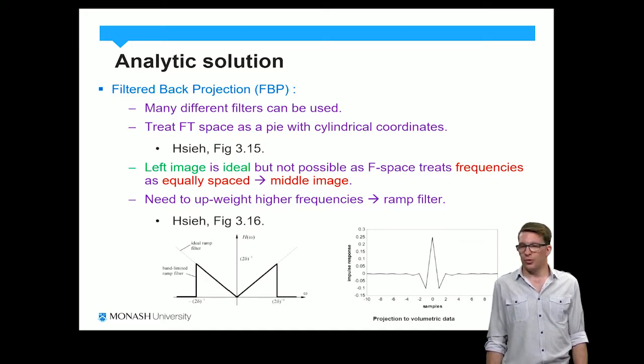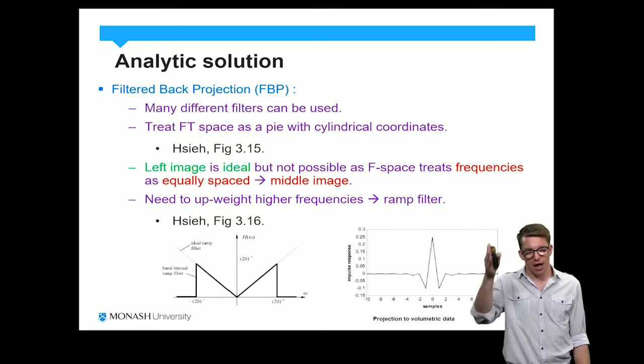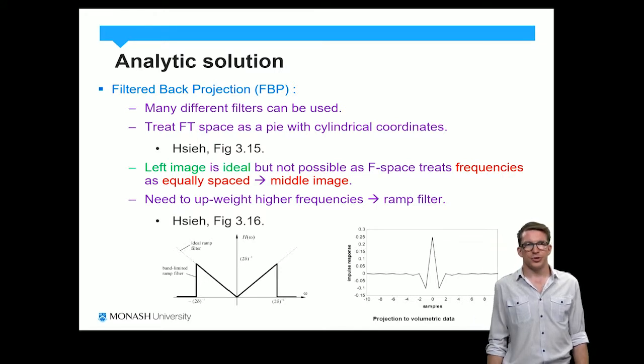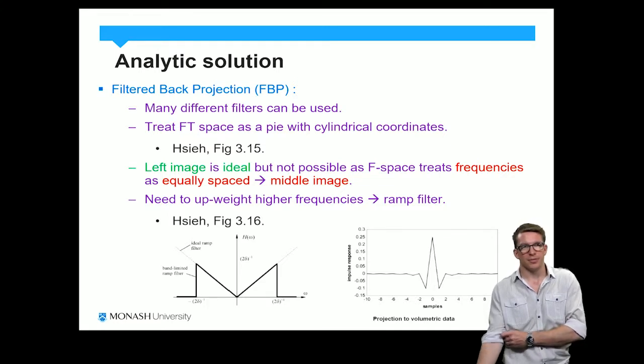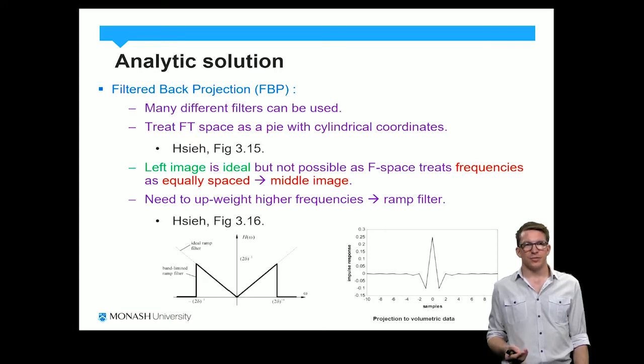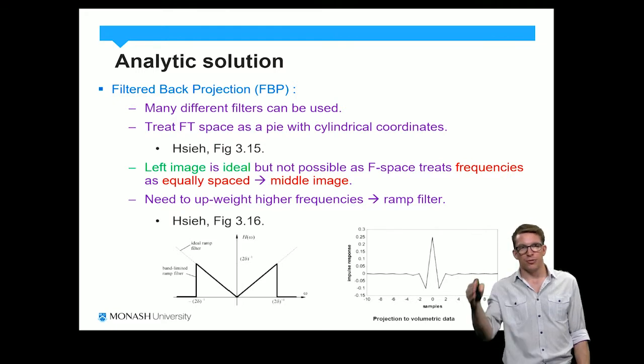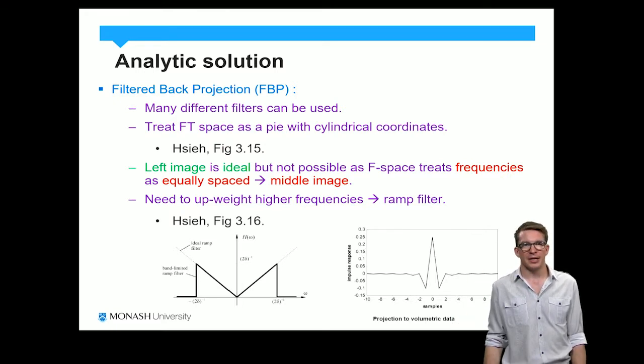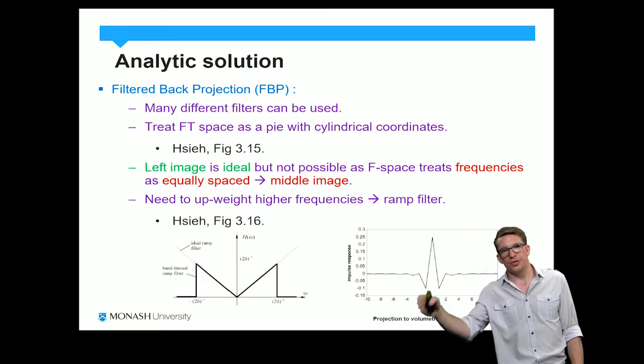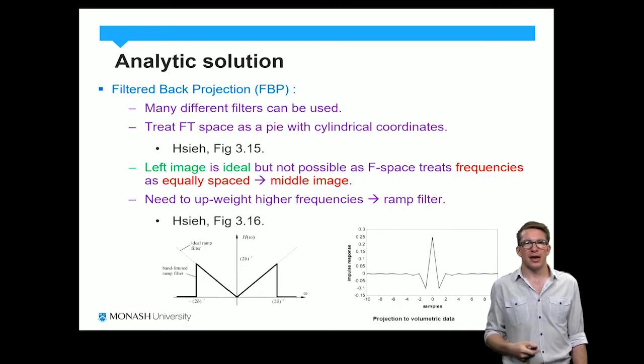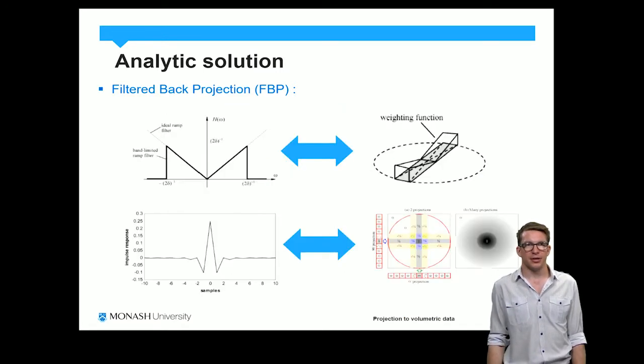Now we also saw that if we apply a filter like this with a hard cutoff, one of the issues is that we get artifacts in our reconstruction. Whenever you're doing Fourier transforms, we don't like harsh cutoffs in the frequency domain. We have to smooth that edge out, and we did that by combining the ramp filter with a Butterworth filter of some kind or a Hann filter, and smoothed that over at high frequencies so it curves off gently back down towards zero, and it stops the ringing artifacts appearing in the resultant image.